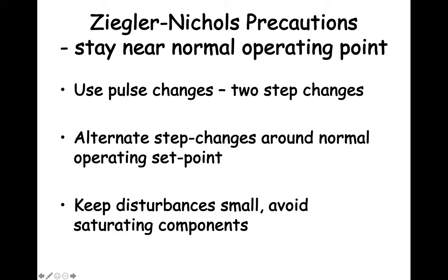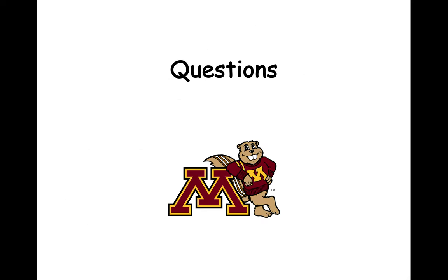When working with real industrial processes, it is important to take some precautions. Here are three recommendations when adjusting a process to collect data to be able to use the Ziegler-Nichols method. Pulse changes are recommended — when you step up to create one step change and step down to create a second step change, by alternating step changes around the normal steady state conditions, you avoid getting far from normal conditions. Also, by using small disturbances, you avoid saturating system components. This brings us to the end of this lecture. Please write down any questions you have and bring them into class.